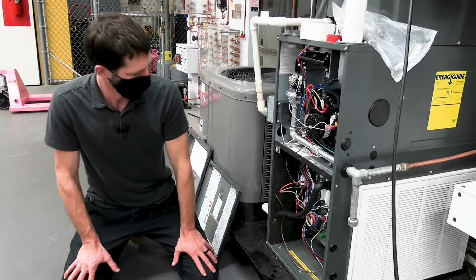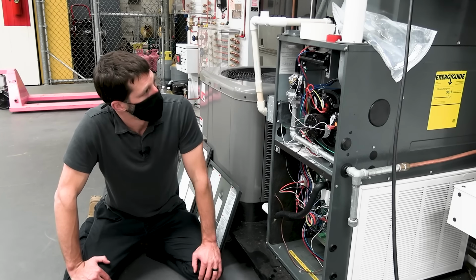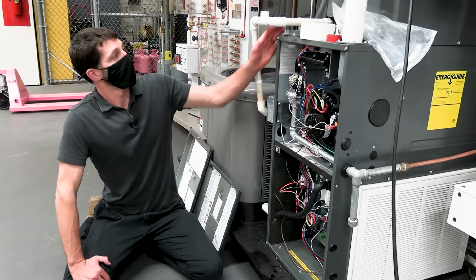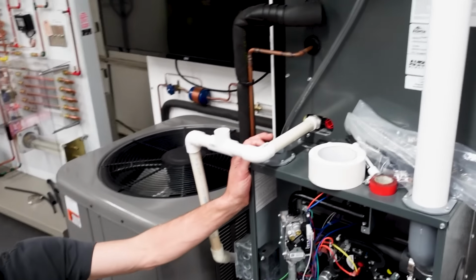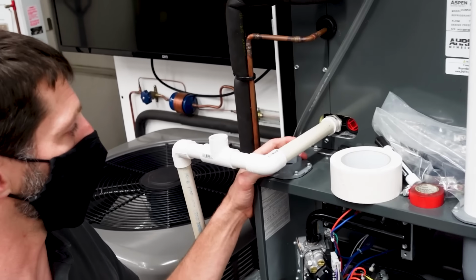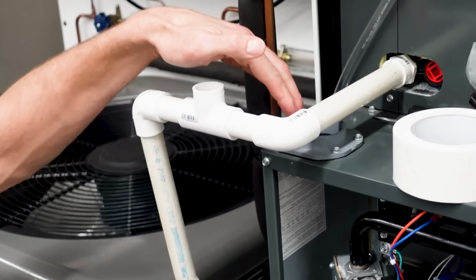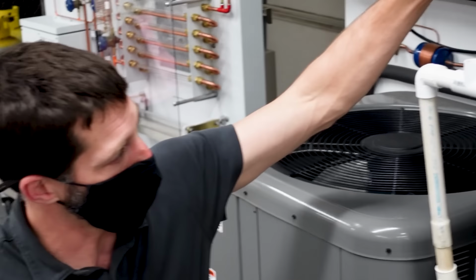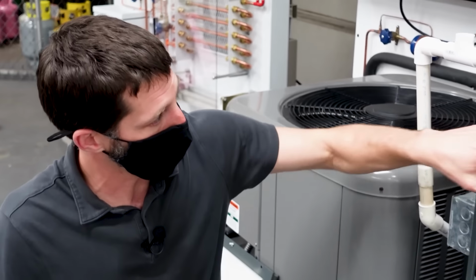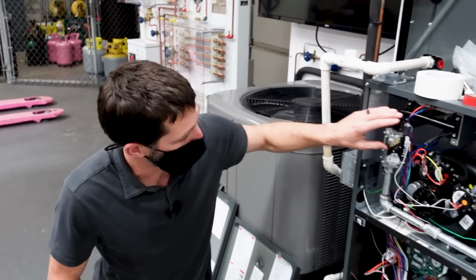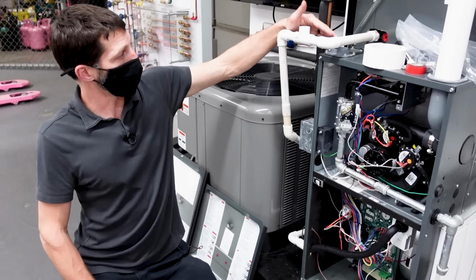Great. Awesome. Talk a little bit about the intake that you'd normally have in a high efficiency. So what I would normally do is I would never really, me personally, leave this blank. I would run this to the outdoor air because I don't want the inside of the building to turn it into a vacuum, because that's what's going to happen. It has to draw its combustion air through here into the combustion chamber, which is located right here. So I would always run that out.